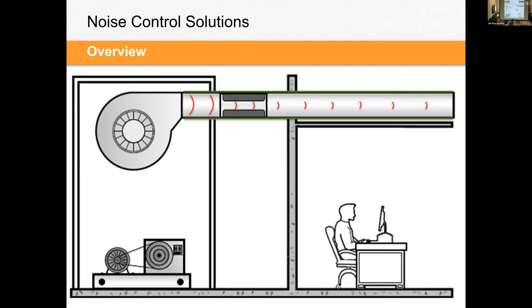You need to observe the four duct lengths from the fan. Great question. Ideally, you would take that into account when you have a less than ideal duct element, whether it's a fan, a junction, an elbow, a transition. Silencers are tested to a standard under ideal conditions, a very long straight run of duct, with the silencer in the middle. When you have a fan upstream or downstream of that silencer, the location of the fan is going to impact the pressure drop of that silencer.